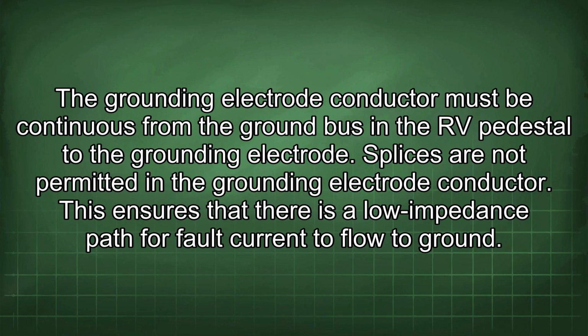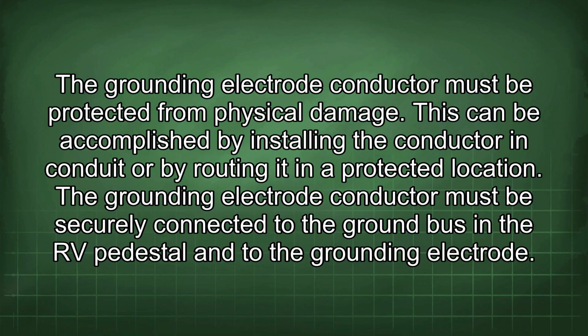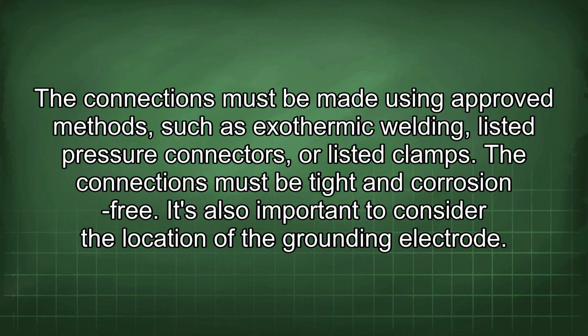The grounding electrode conductor must be continuous from the ground bus in the RV pedestal to the grounding electrode. Splices are not permitted in the grounding electrode conductor. This ensures that there is a lower impedance path for fault current to flow to ground. The grounding electrode conductor must be protected from physical damage. This can be accomplished by installing the conductor in conduit or by routing it in a protected location. The grounding electrode conductor must be securely connected to the ground bus in the RV pedestal and to the grounding electrode. The connections must be made using approved methods such as exothermic welding, listed pressure connectors, or listed clamps. The connections must be tight and corrosion-free.